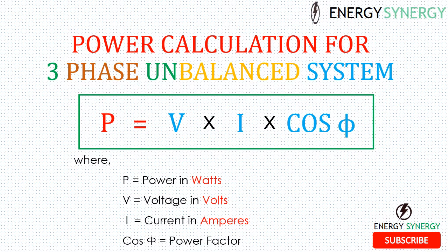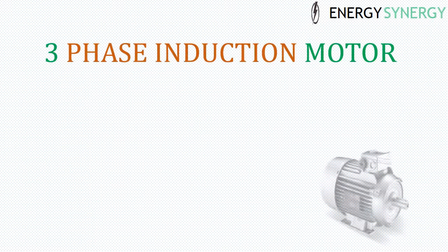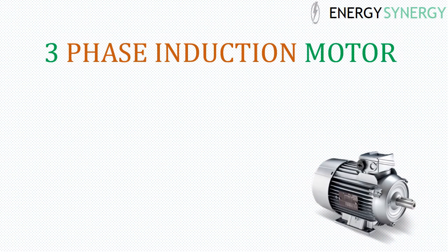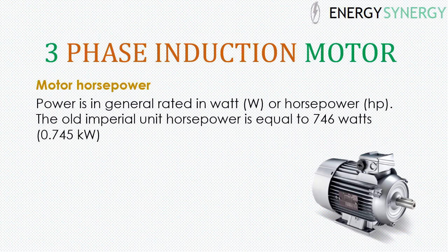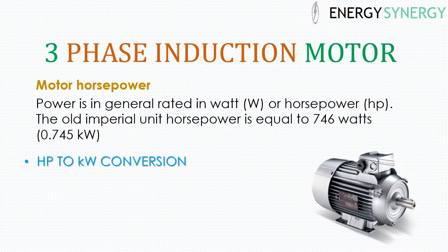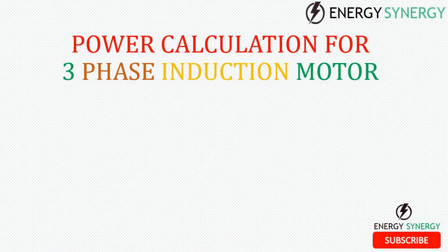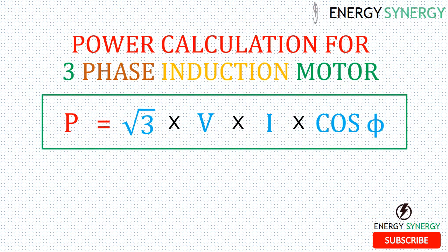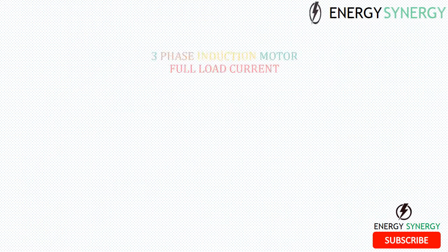Three-phase squirrel cage induction motors are widely used as industrial drives because they are self-starting, reliable, and economical. They are most commonly rated in kilowatt and HP (horsepower). The old imperial unit horsepower is equal to 746 watts, that is 0.745 kilowatt. To convert HP to kilowatts, divide the HP value by 1.341. The power calculation formula for a three-phase induction motor is: Power = √3 × V × I × cos φ. This method is used both theoretically and practically in industries.